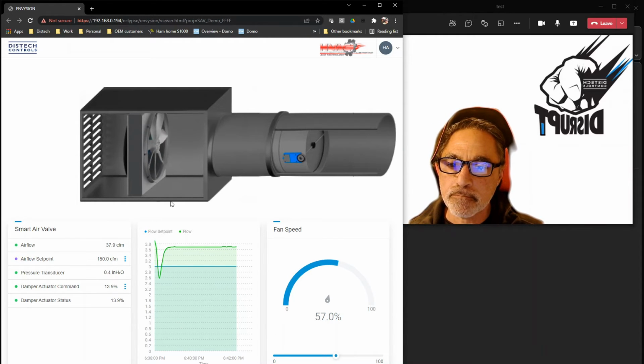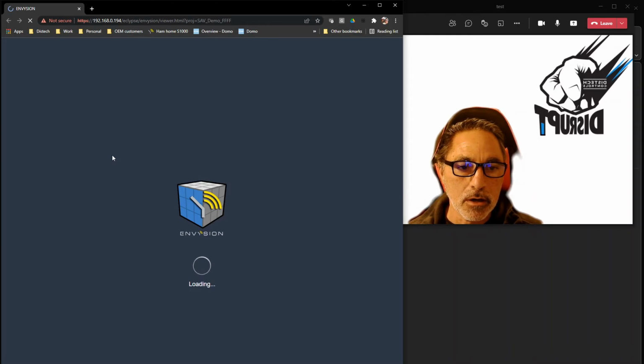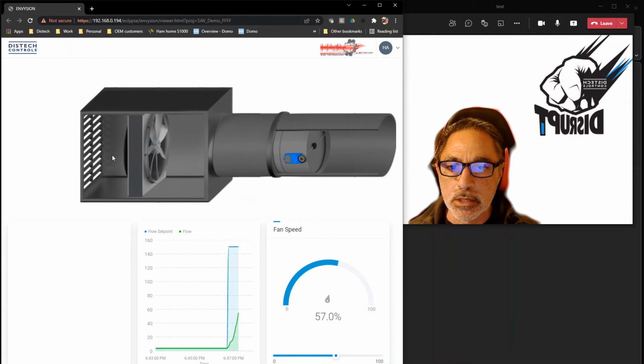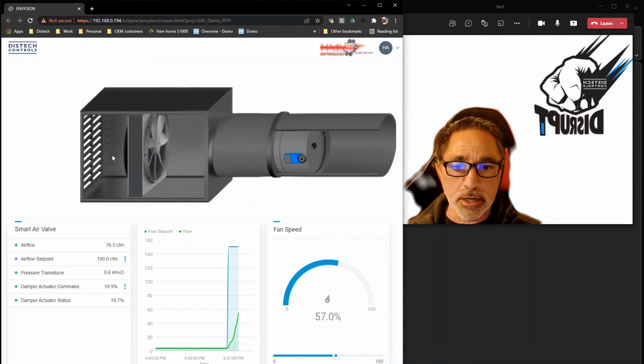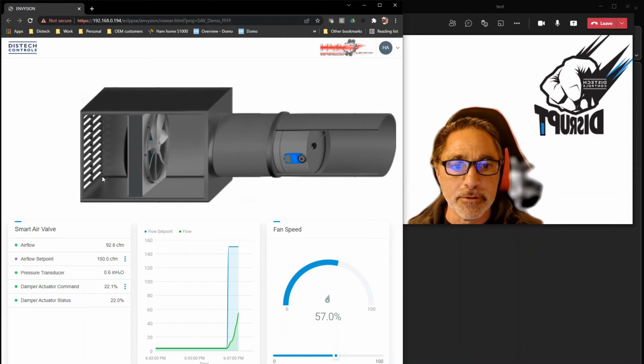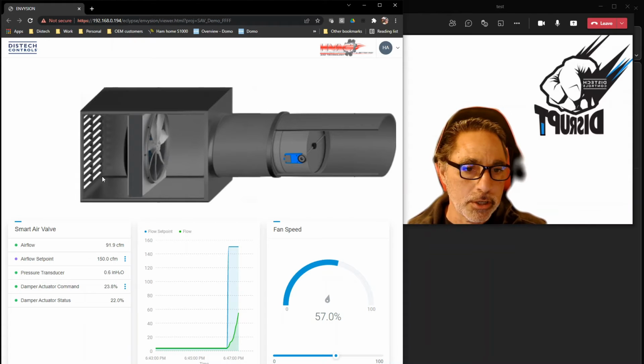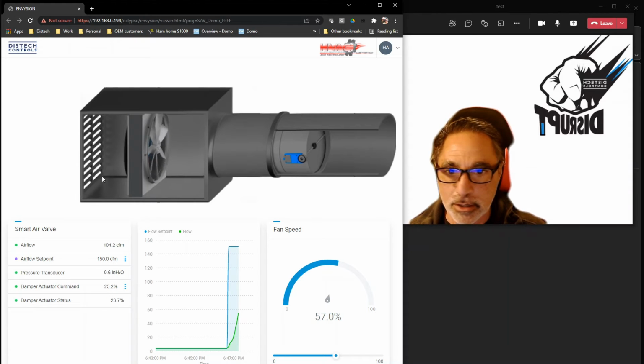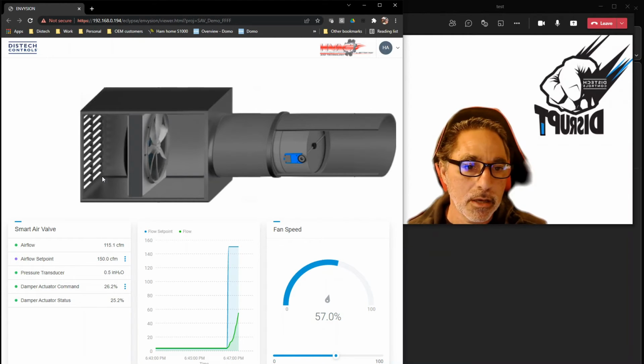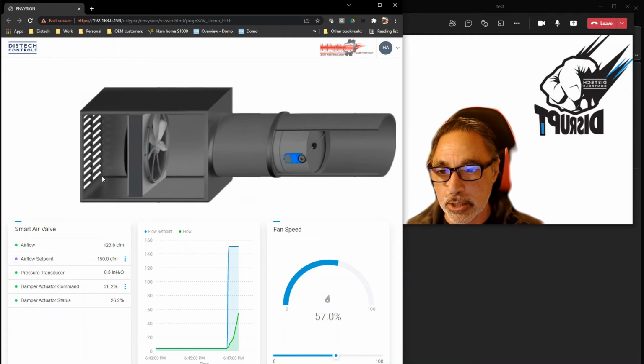57%. My trend log, I'll probably have to apologize. I'm going to do a little refresh on my screen here just to make sure the trend log refreshes so you can actually see what's going on. And one thing you should also recognize here, I'm running on a web browser using Chrome. All our devices have web services built into them. The graphics are built inside the controller. All the trends, alarms, and widgets are all inside the controller. So I don't have any kind of supervisory layer here from a building automation system that I'm getting access to this VAV box. This makes it very easy for me to demo this and provide you this information.